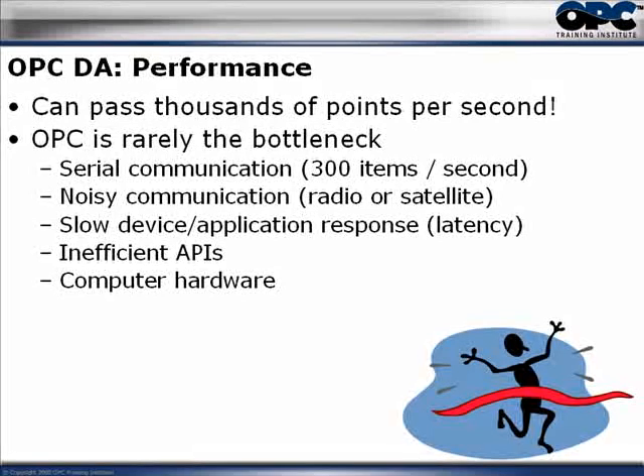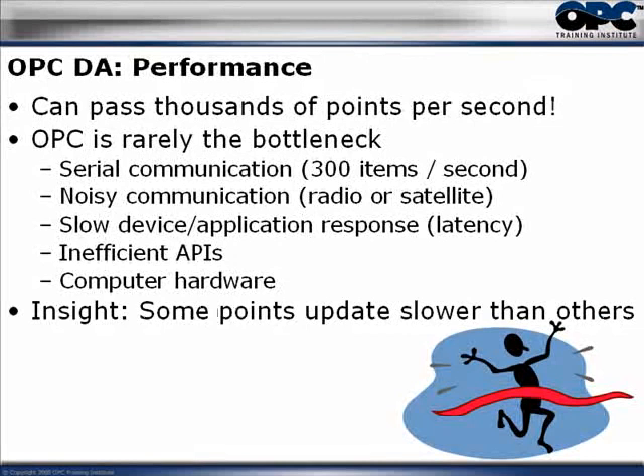Noisy communication, latency, or inefficiencies will cause a slowdown that appears to come from the OPC server itself, but OPC will not be the bottleneck — the bottleneck will be elsewhere. Computer hardware can also be an issue. Just remember: some points update slower than others — temperatures and levels don't typically update nearly as fast as flows and pressures.